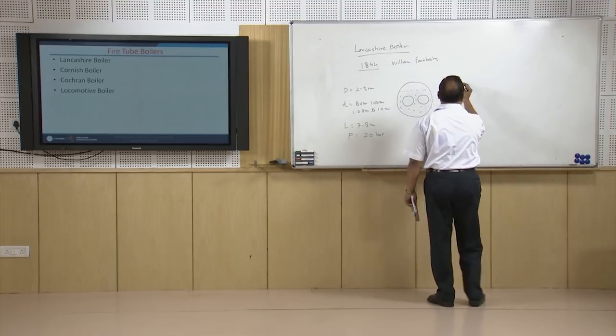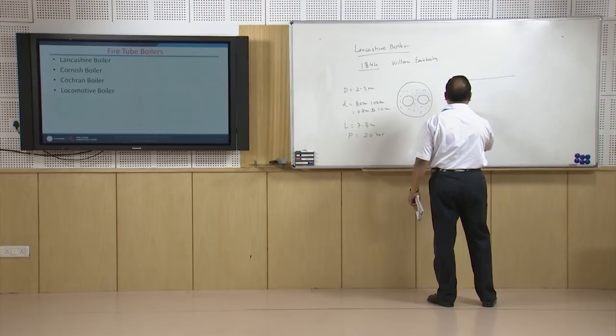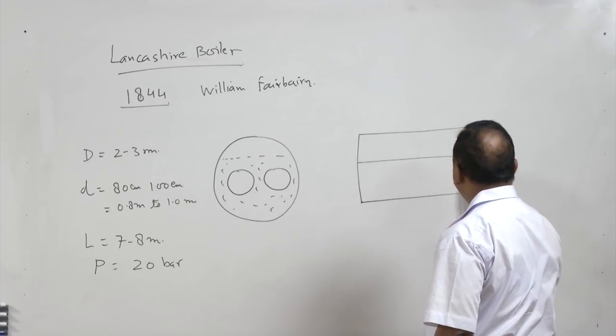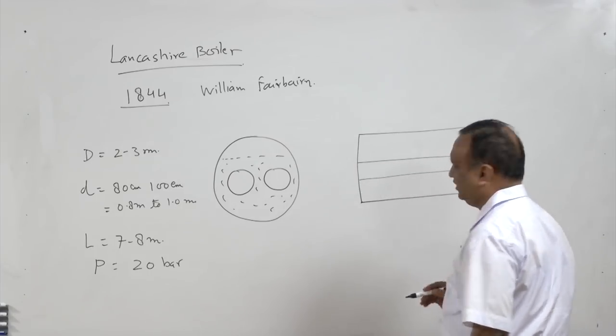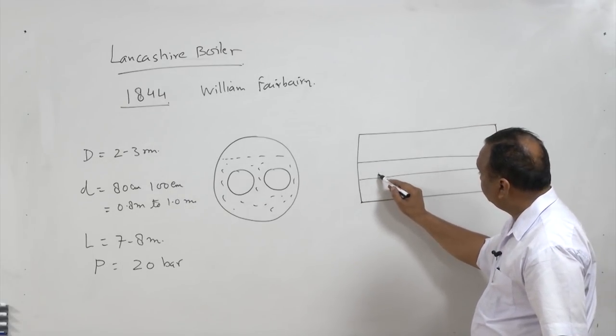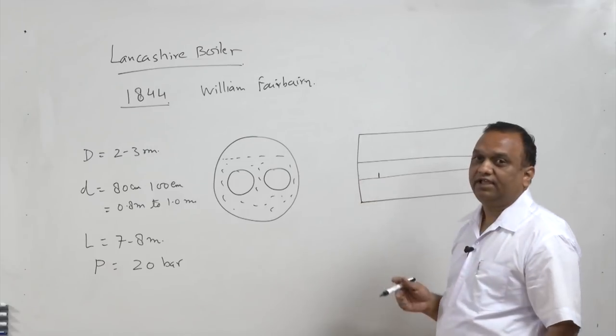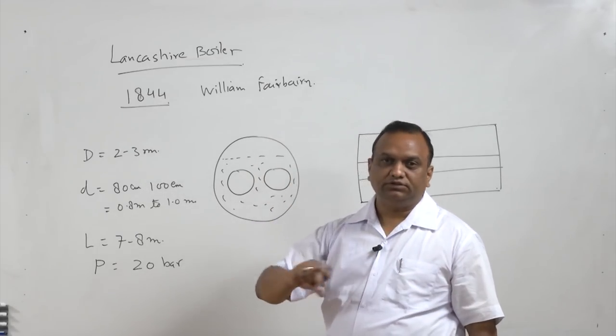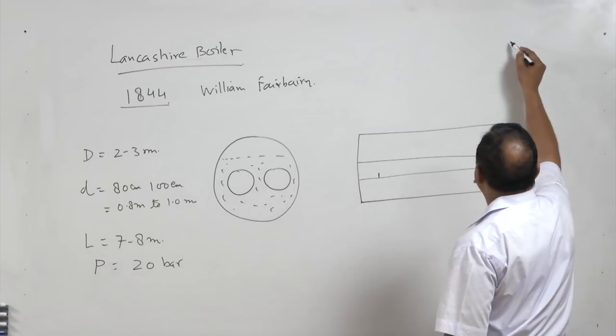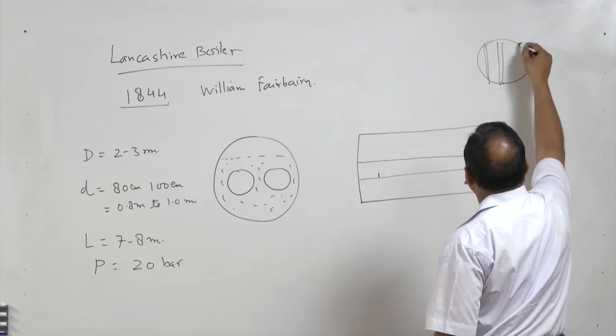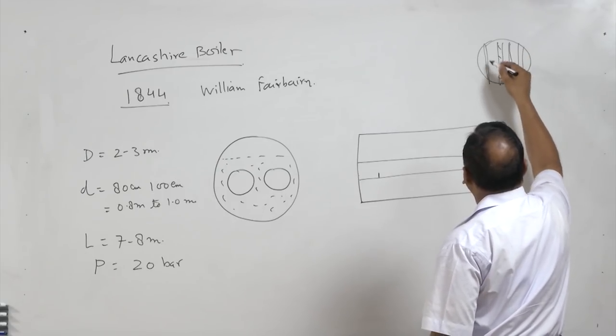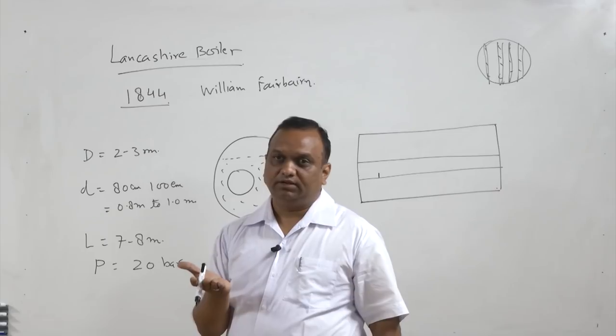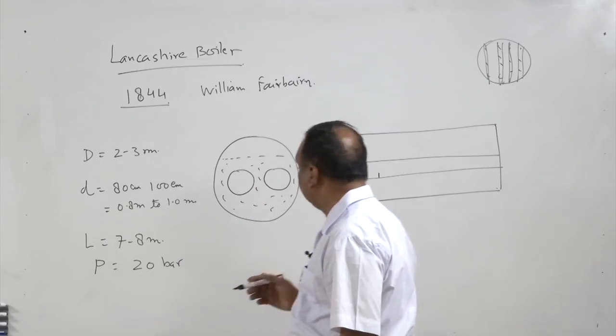If I draw the elevation of this boiler — because there are two tubes — from the elevation they will appear to be a single tube. Fuel is burned in a portion where there is a grate. A grate is a perforated platform or a platform having a number of rods, and on this platform the fuel is burned. Below the grate there is an ash pit from where the ash can be removed.